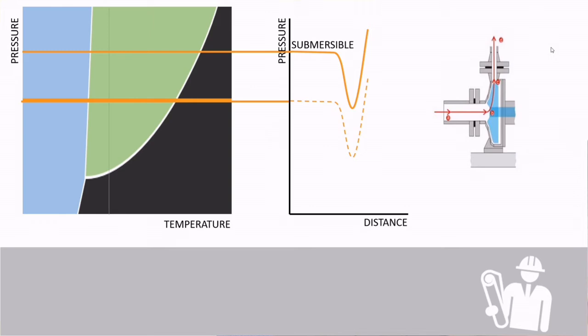However, when the pump needs to do a suction lift or has a lot of friction or velocity within the suction pipe work, you can see that the pressure drop reaches the vapor pressure, and as we know, this is when cavitation occurs.